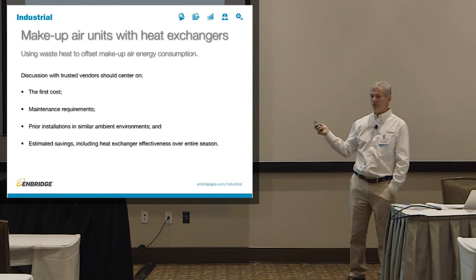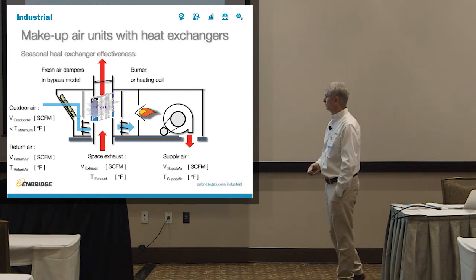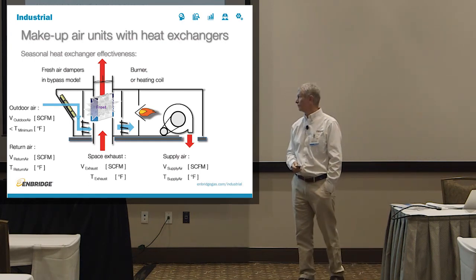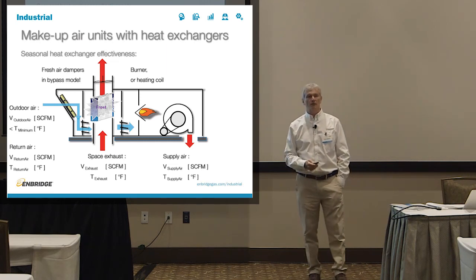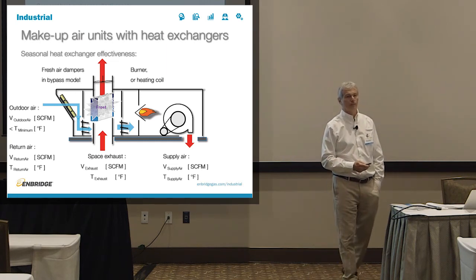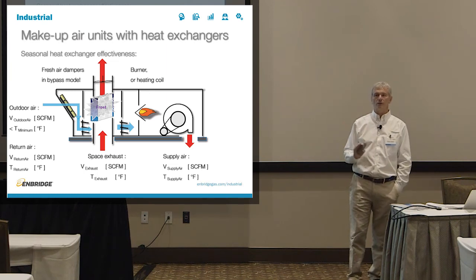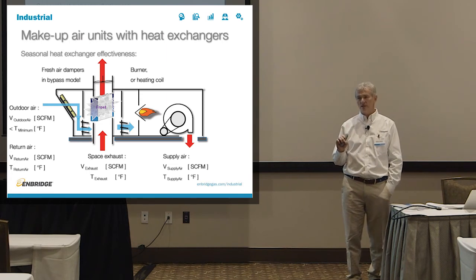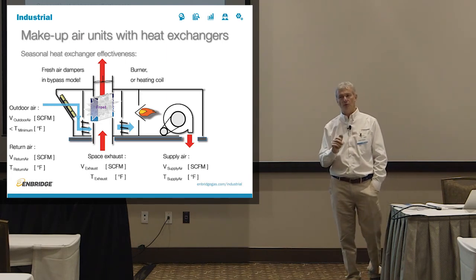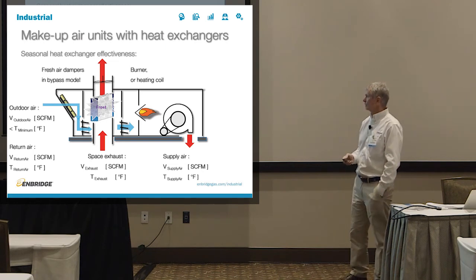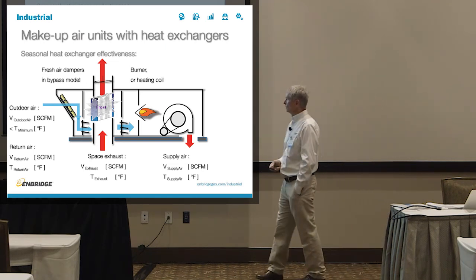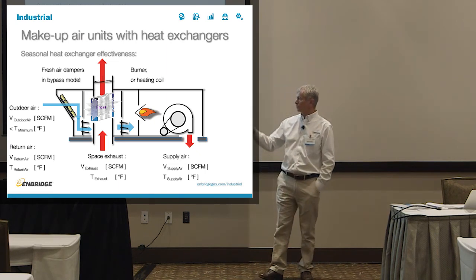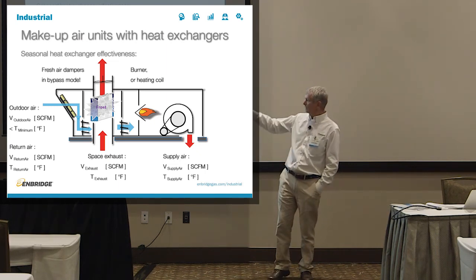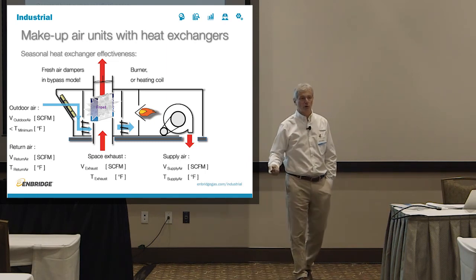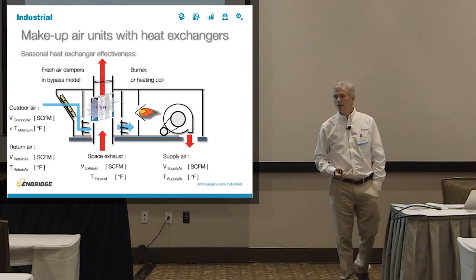It's one thing that you have to be very cognizant of and aware of when you do this kind of equipment. Because what happens usually is at some point you will create frost in this heat exchanger. Different vendors have different ways of dealing with this, and it's really important that the vendor you choose understands, and you understand, the repercussions of that particular way of dealing with it. So for example, one vendor that I know of will bypass the heat exchanger with a set of dampers, and your burner will start working just like a normal burner without any heat exchanger.